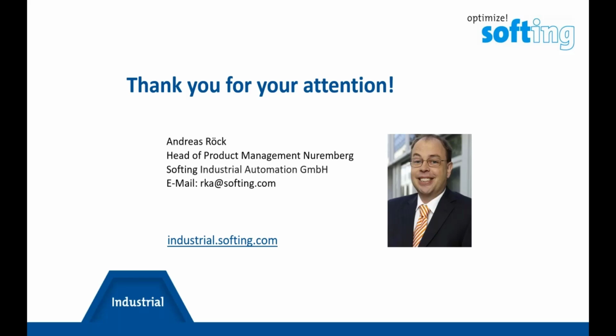We have a second limitation. It's a maximum of 10,000 data points which are possible to use in our add-ons at all. Add-on means MQTT, database, to file exchange functionality. In all these, I will say, functionalities, add-ons, you can only use maximum 10,000 data points. And the number of connections is limited to 50.